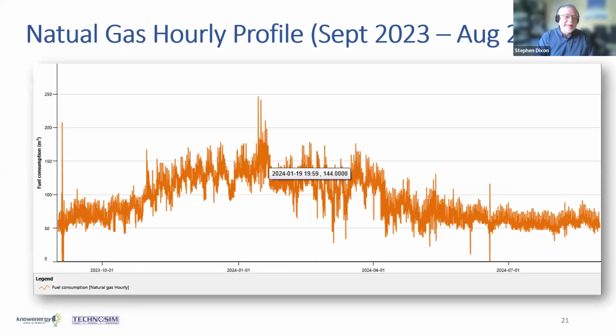Same thing for gas. That data is available hourly for many facilities now. If you have to electrify that facility, this curve is really valuable because it tells you how big that heating system has to be. If you assume your boilers tell you how big it has to be in the future, maybe that's not the case if you've made changes. So understanding your real heating load is really important, and these types of graphs are really useful.